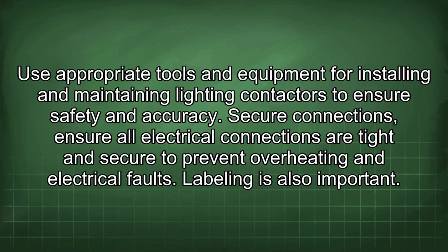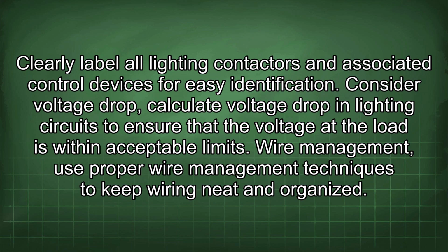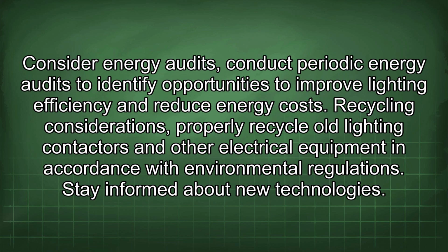Secure connections. Ensure all electrical connections are tight and secure to prevent overheating and electrical faults. Labeling is also important. Clearly label all lighting contactors and associated control devices for easy identification. Consider voltage drop. Calculate voltage drop in lighting circuits to ensure that the voltage at the load is within acceptable limits. Wire management. Use proper wire management techniques to keep wiring neat and organized. Consider energy audits. Conduct periodic energy audits to identify opportunities to improve lighting efficiency and reduce energy costs. Recycling considerations. Properly recycle old lighting contactors and other electrical equipment in accordance with environmental regulations.